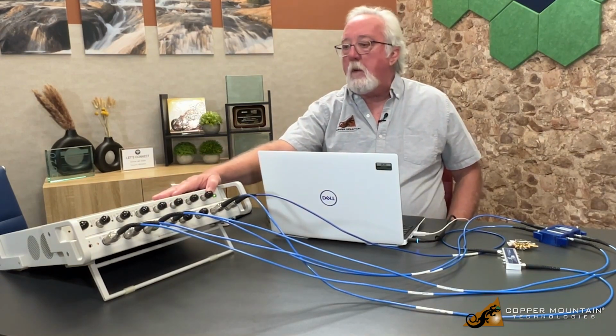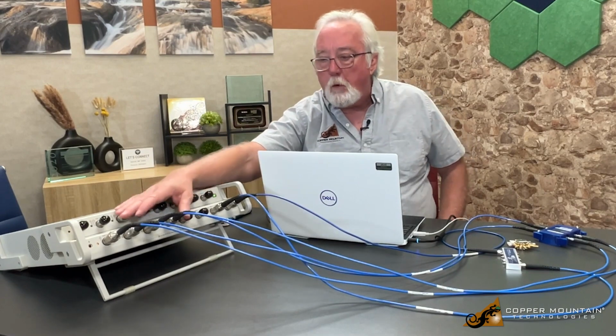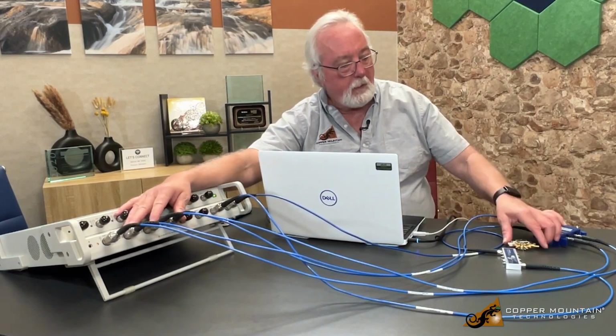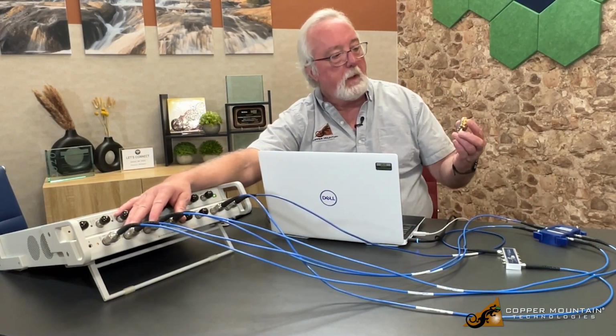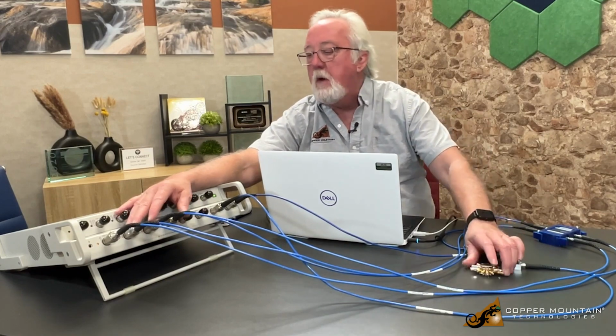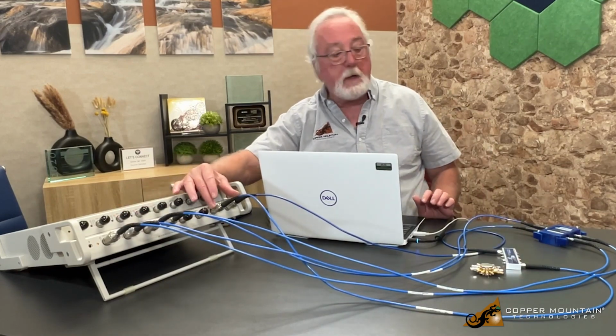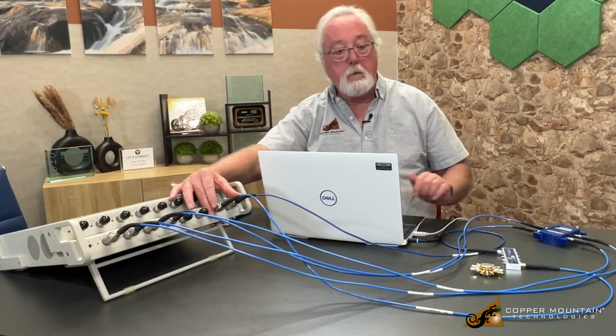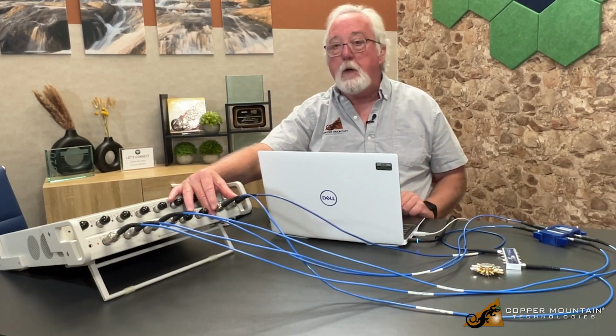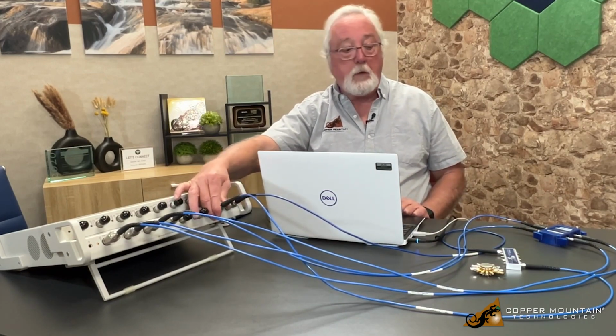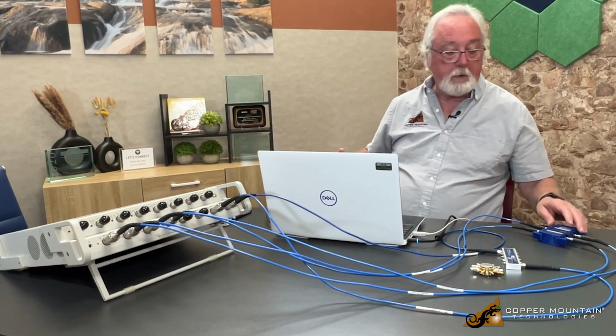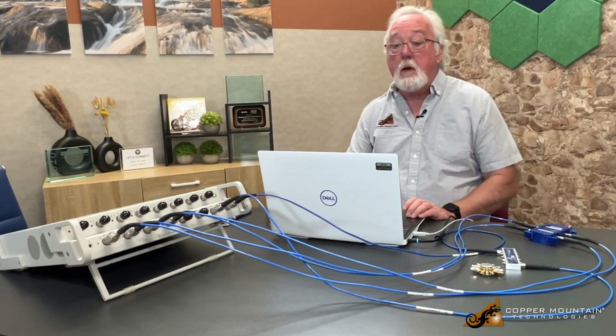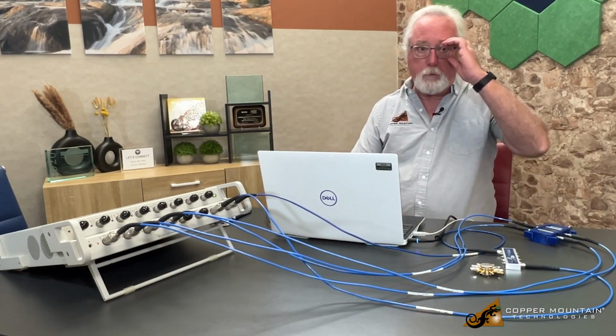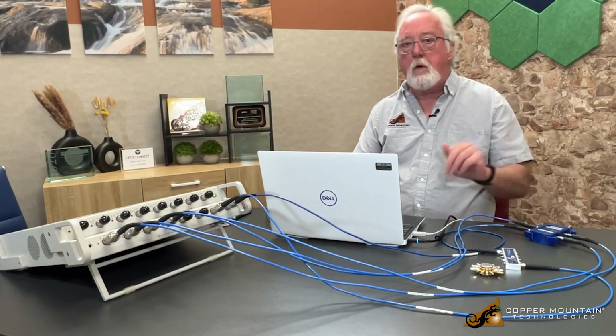Today I'm going to do a calibration of the first 4 ports to measure a splitter, and then I'm going to use ports 7 and 8 to make a 2-port measurement of a filter at different frequencies. So I'm going to set this up. Let's do that calibration. I'm going to use 2 channels because the frequencies of the measurements are different.